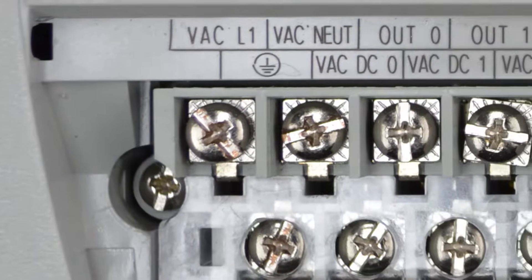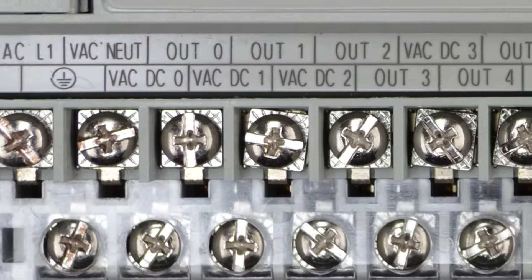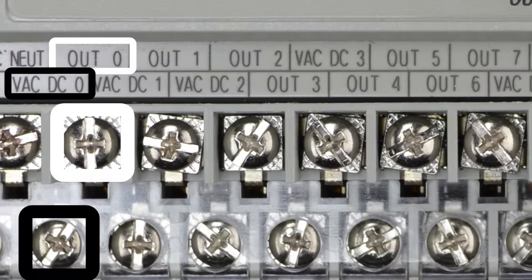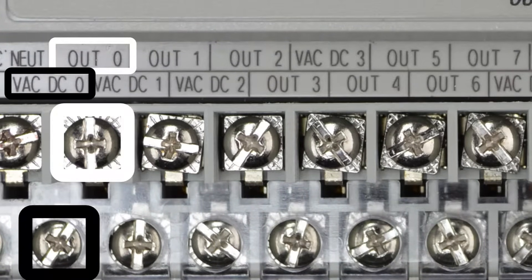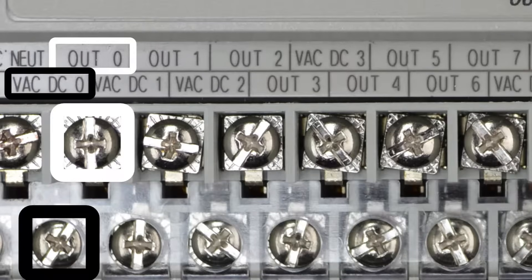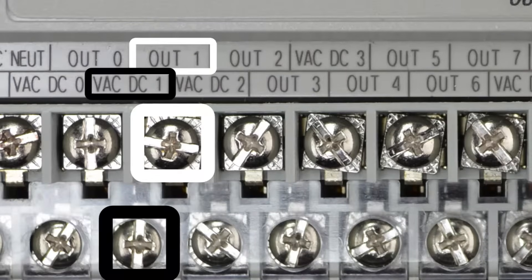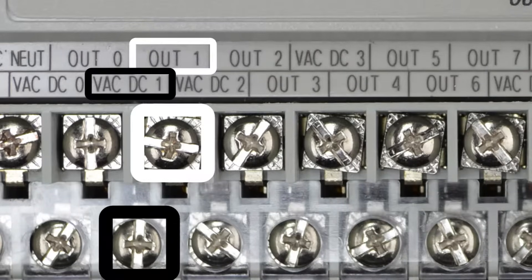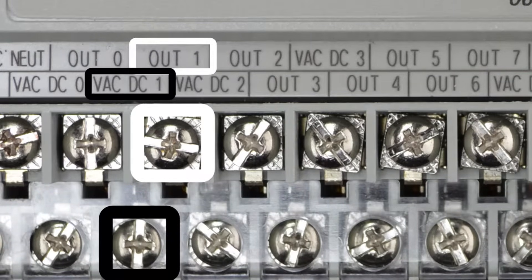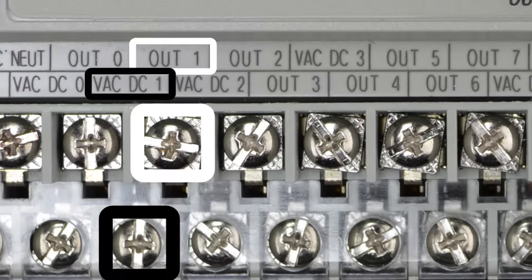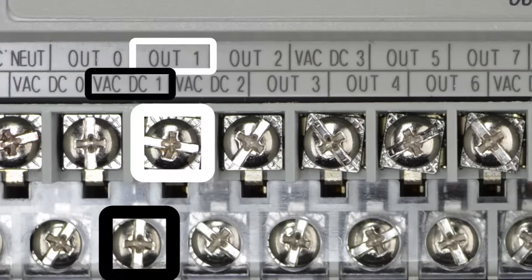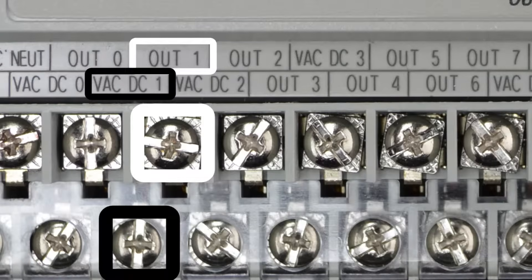To the right of that, we have our first set of output terminals. This particular micro is a relay output model that supports both AC and DC. Notice that outputs 0 and 1 each have their own VAC-VDC power terminal. So they're each isolated from each other and the rest of the outputs.